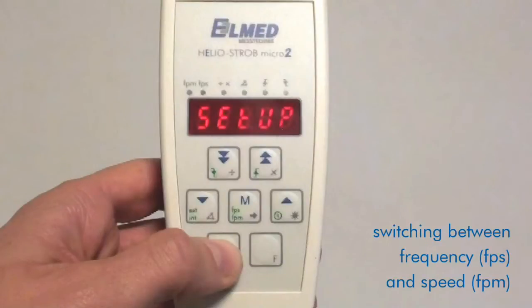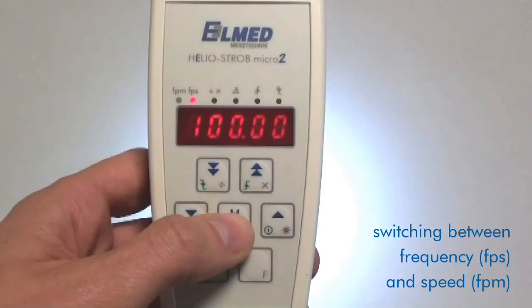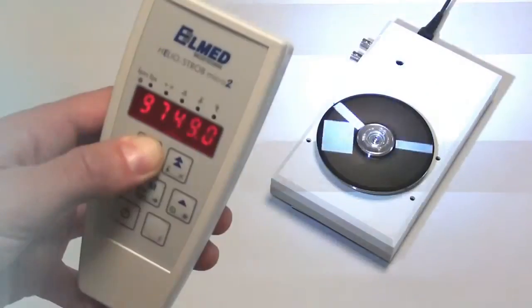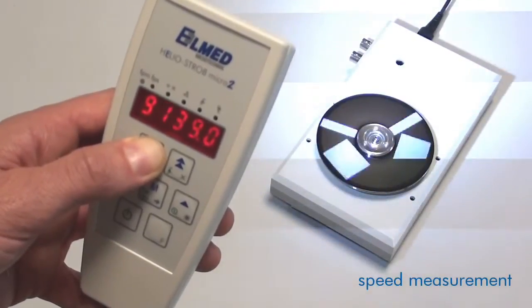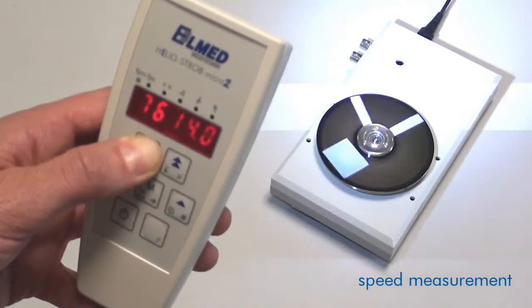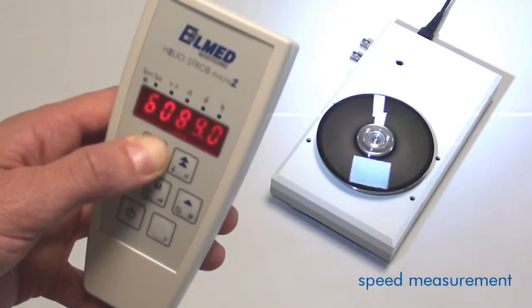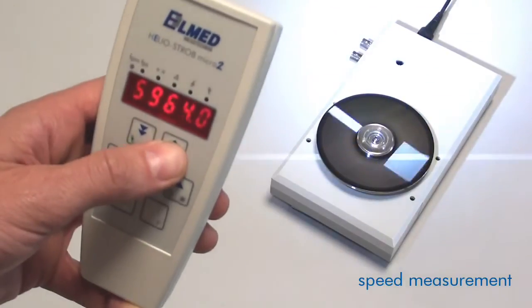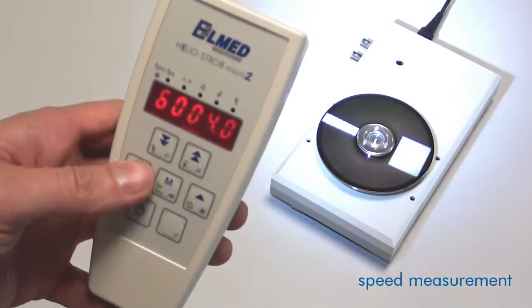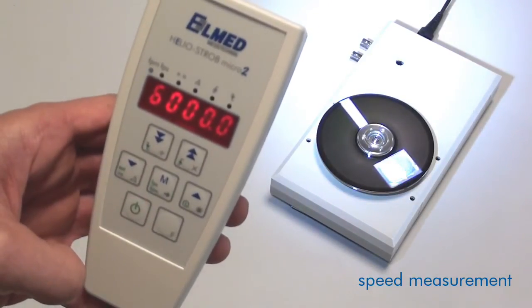For the activation of the setup mode in green symbols, please press the ON key while the device is switched on. By pressing the M key FPS and FPM, you can now change between the modes frequency and revolution speeds. The following example shows how easy it is to measure revolution speeds with the HelioStrobe Micro 2. Highlight the object with the maximum possible frequency or object speed, then continuously reduce the frequency until the object seems to come to a standstill. The measured number of revolutions is shown on the display.